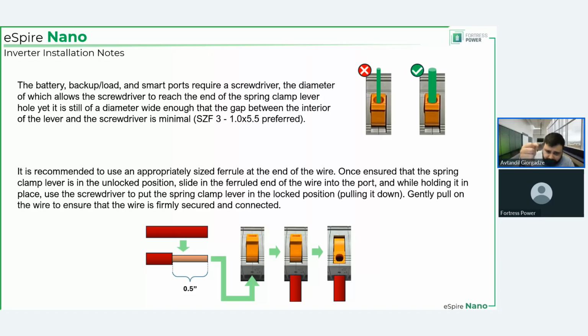So all the way up to open it and all the way down to close it. And neutral position is not the indication that it's actually closed or open, regardless of where the clamp is oriented, upwards or downwards. It has to click in place. And another thing, once you have put the conductor in place and closed the clamp, give it a gentle tug. Make sure that it's safely in place and it's not going to fall out.